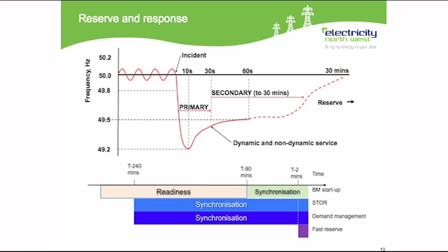With slide 14, I'm trying to explain really how we intend to provide primary and secondary frequency response within the CLASS project. So looking at the little wiggly line at the top left-hand corner, system frequency goes along fairly steadily at around 50 Hz. But if we lose a large power station or we lose the cross-channel link to France, then system frequency falls very quickly. And as we outlined in the video, if it falls too far, then bad things can happen, and we need to manage the electricity network in real time so that doesn't occur. So currently that's done by large standby generators, and what we intend to do using CLASS is provide very fast sub 1 second frequency response using primary transformers. And we'll show probably at a more technical seminar in the future exactly how we intend to do that.